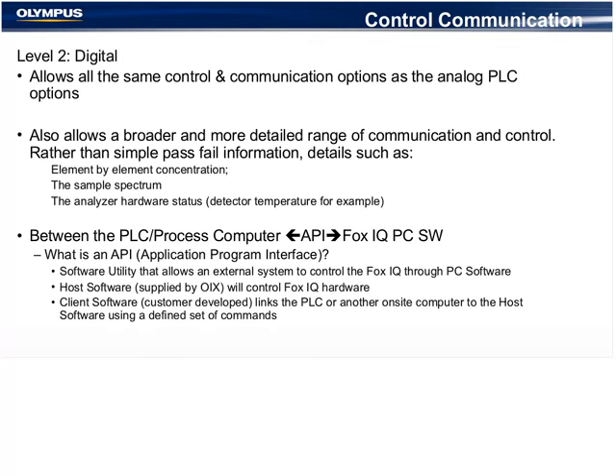Second kind of control communication is digital. The digital allows the same exact sorts of control options as the analog channels would. Also, we've got a broader and more capable ability to communicate. We can give you element by element concentrations, the X-ray spectrum if you want that sent off, the analyzer hardware status. Some people want to know how the system's doing and track that over time. Between the PLC process computer and the Fox IQ PC software, we have something called an application program interface, an API. And this is a software utility that basically allows your PLC to query and control our PC software directly. There's a host part to that and a client part to that that reside on the PC.